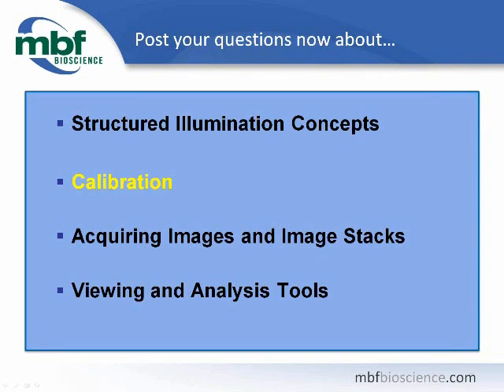Kamari wants to know if they can create a three-dimensional image of a neuron — we're going to demonstrate that in the next session. In your ApoTome setup you'll have a special filter cube; this is purely for phase calibration of the ApoTome system and is the only time you'll use this filter cube, used only with the mirror slide.